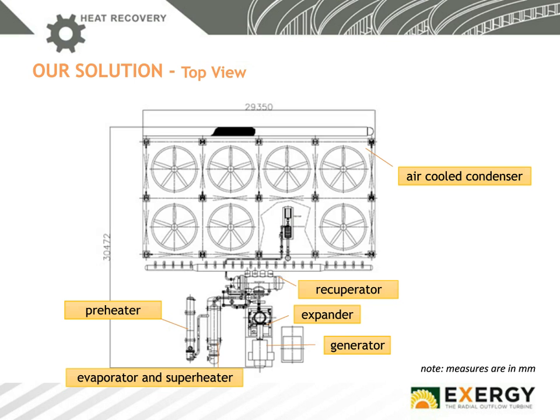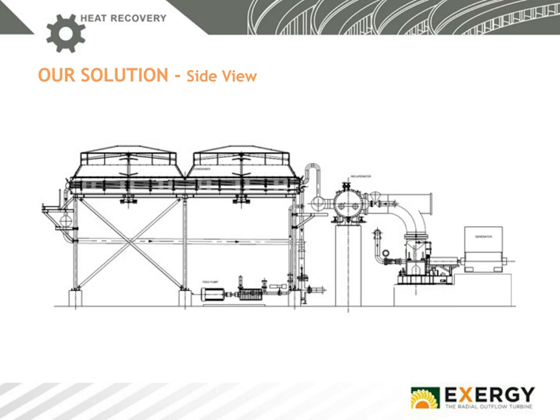So in this case, for example, we have 4 bays, 8 fans of air-cooled condenser. We have an ORC, you can see in this layout, composed of expander, generator, hot heat exchangers, so preheater, evaporator, and superheater, and recuperator. As you can see, this is as small as 30 meters times 30 meters. So it's really a very simple and compact system to produce 5 megawatt more for this plant. Here you can see a side view of the system. Again, this is quite a small unit.